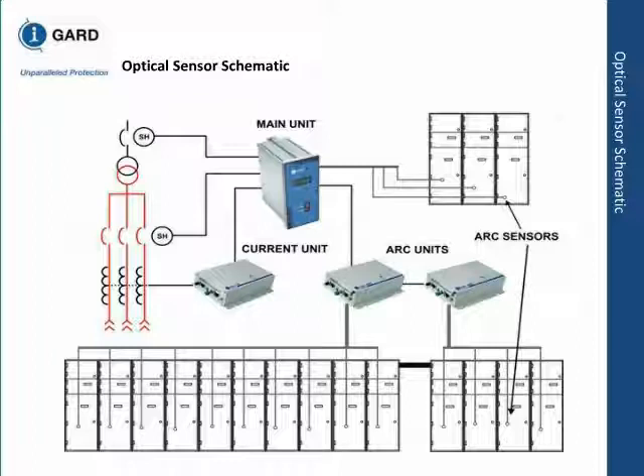Of course, keep in mind, this is only contingent upon the breakers having been maintained properly so that they'll trip on command. All this is doing, whether it's zone selective interlocking or optical detection, is giving a signal to the breaker to trip. The breaker has to be in proper condition to trip. If it's a DC operated breaker, you need to have control power available.